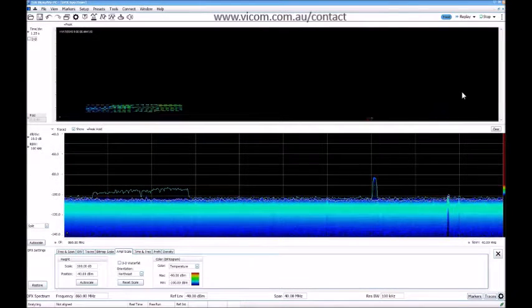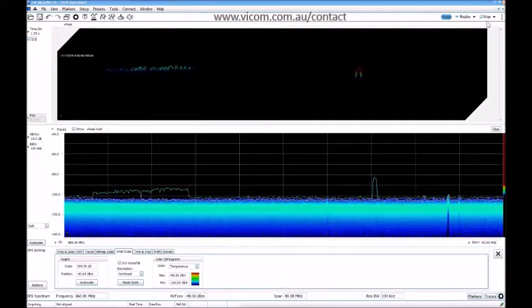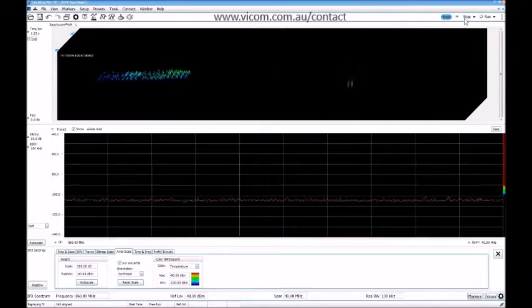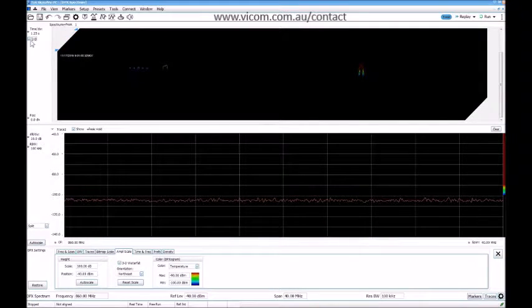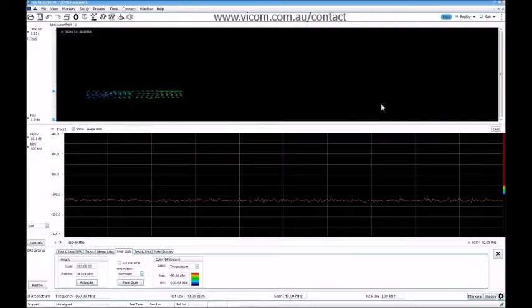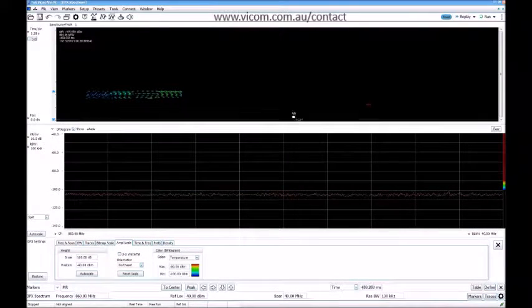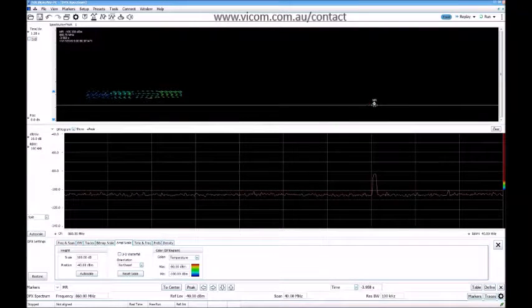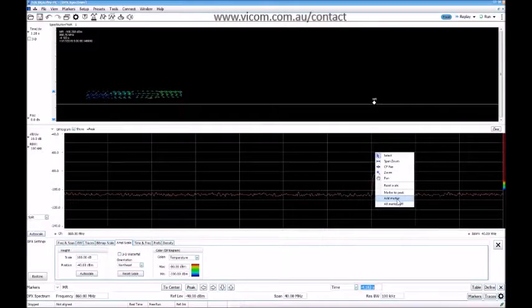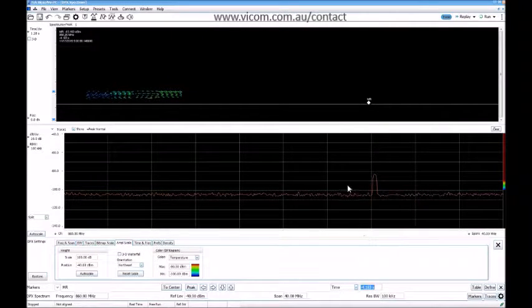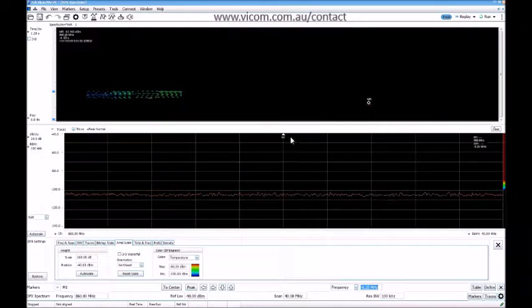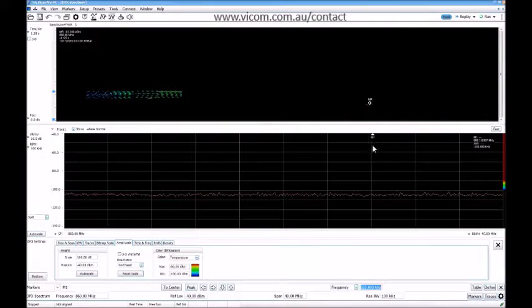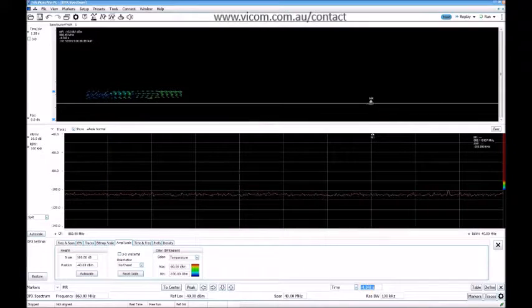You can start doing measurements here also if you like. In this case, what is this pulse? You go here and add marker, and you move in here. You have your pulse here and you have your pulse here. You can add marker, marker to peak. It's probably around 868, which is the open band.